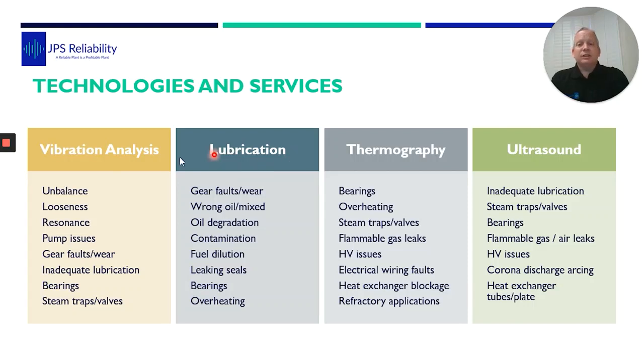I like to keep this slide in because it emphasizes these are the four main technologies. There is obviously motor current analysis and electrical signature analysis used as well, but these are the four main ones that we use, and it shows you that they all have their own detection. For instance, on this failure with the exciter, they were using thermography, and it would pick it up before it failed, but they were really at the point of failure.